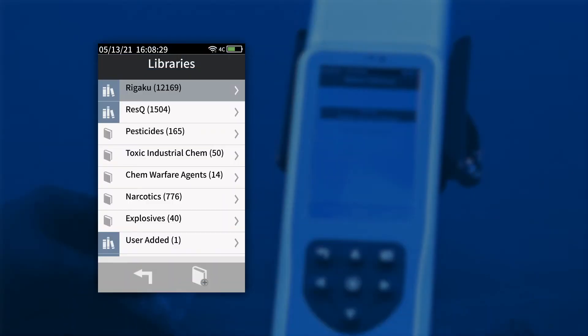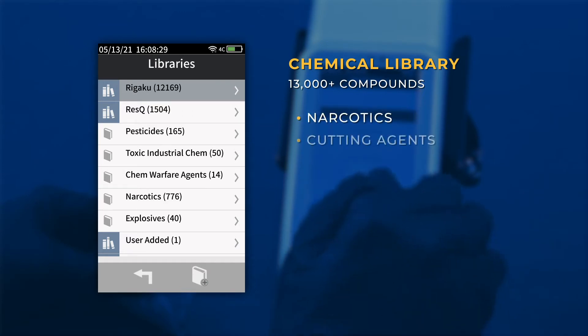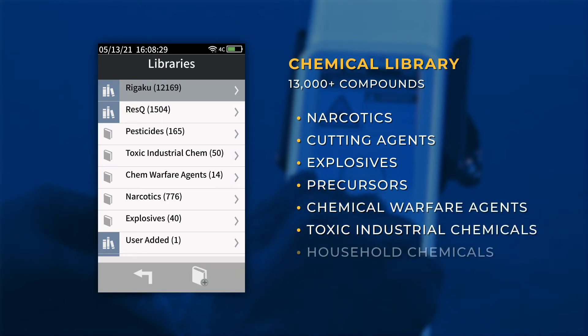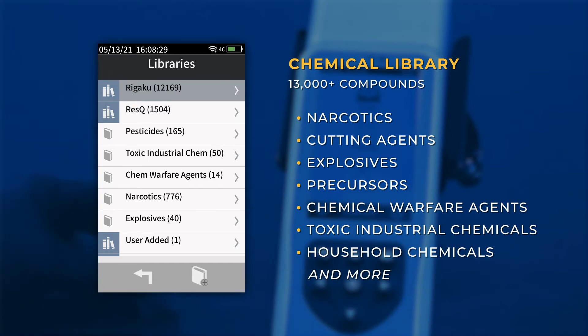Utilizing the 1064 Raman Advantage, combined with a large onboard chemical library of nearly 13,000 compounds that include narcotics, cutting agents, explosives, precursors, chemical warfare agents, toxic industrial chemicals, household chemicals, and more. Coupled with the added benefit of allowing you to easily add new chemicals, the Progeny ResQ broadens the range of materials that you can analyze in the field.